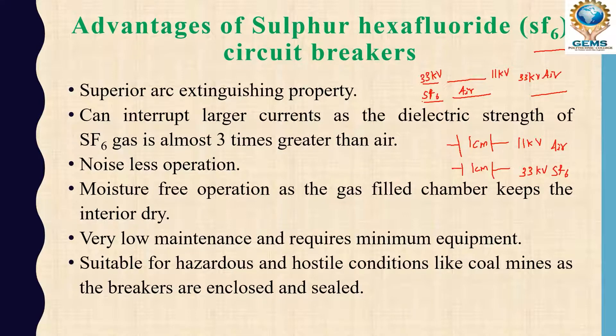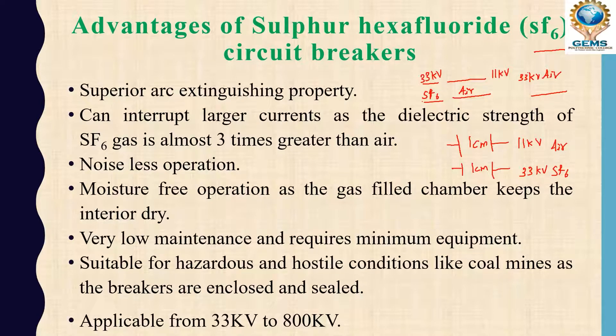It is suitable for hazardous and hostile conditions like coal mines. Since the breaker is enclosed and sealed, we can use it anywhere - even in coal mines where fire is very dangerous. It is also applicable from 33 kilovolt to 800 kilovolt, making it usable across a very wide voltage range. These are the advantages of the SF6 circuit breaker.